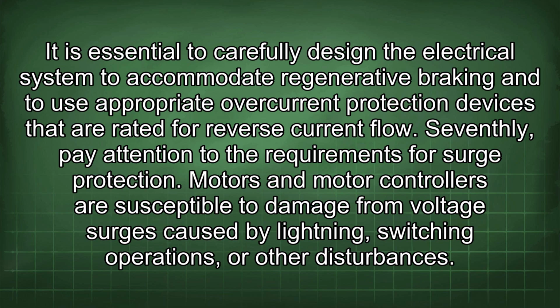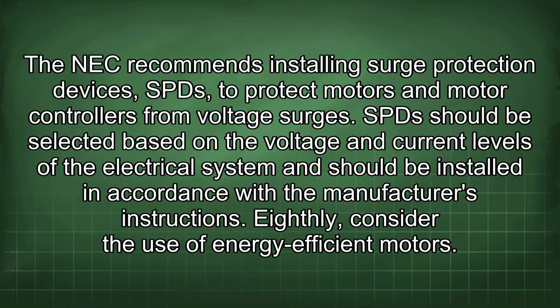Seventhly, pay attention to the requirements for surge protection. Motors and motor controllers are susceptible to damage from voltage surges caused by lightning, switching operations, or other disturbances. The NEC recommends installing surge protection devices, SPDs, to protect motors and motor controllers from voltage surges. SPDs should be selected based on the voltage and current levels of the electrical system and should be installed in accordance with the manufacturer's instructions.